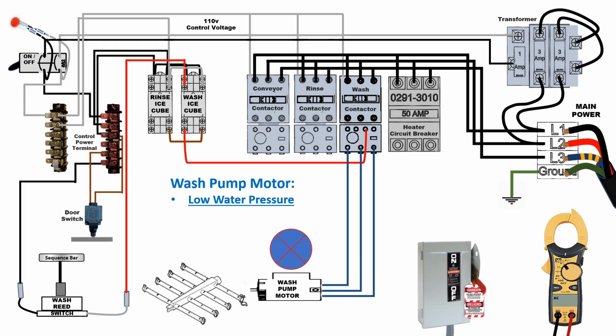Next, to reverse the polarity of a three-phase line on motors, all that is required is that you reverse any two of the hot legs to correct the problem. Reversing any two hot legs. If we took L2 and L3 and reversed them, L1, L2, or even L1, L3, reversing any two of the hot legs will reverse the polarity of the motor. This can be done at the bottom of the contactor. You can correct this by reversing the lines on the top of the contactor, or you can reverse the lines at the motor itself.